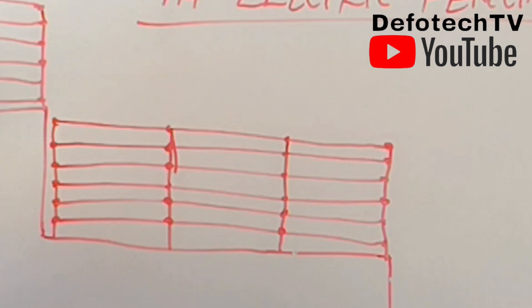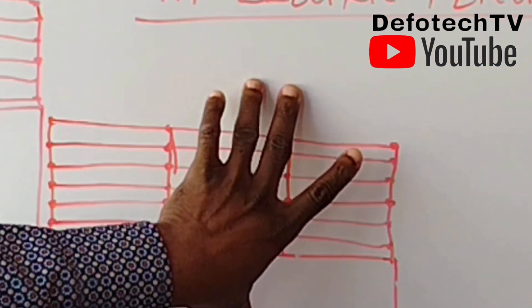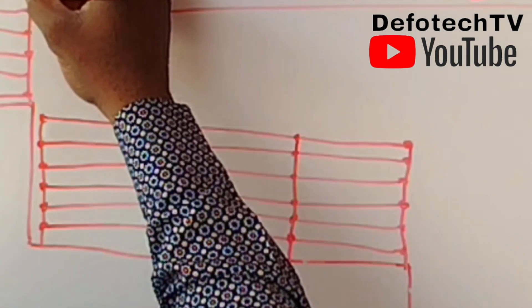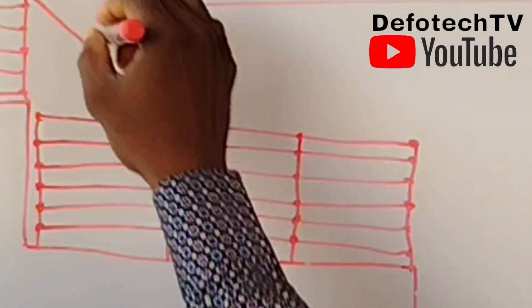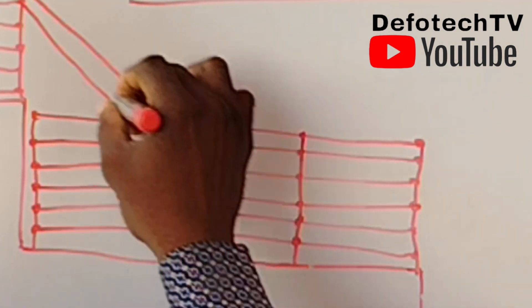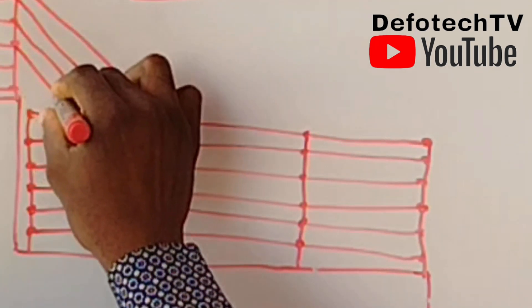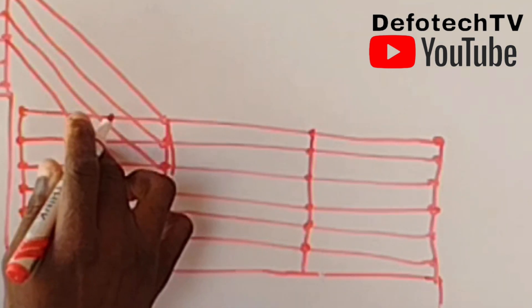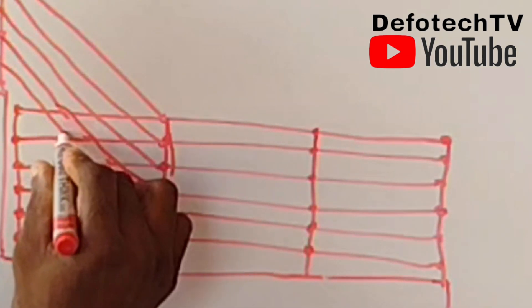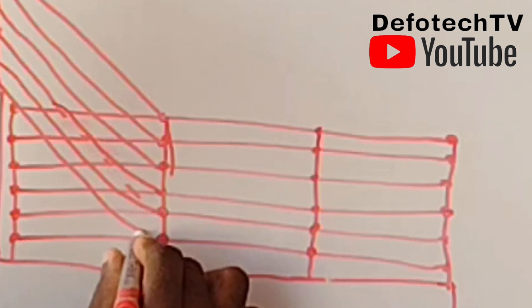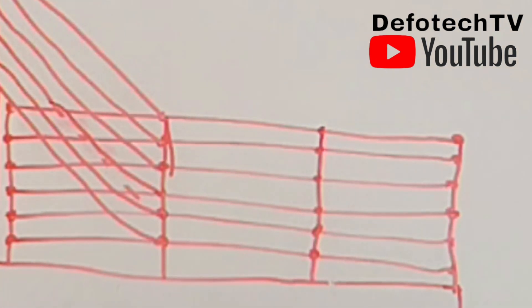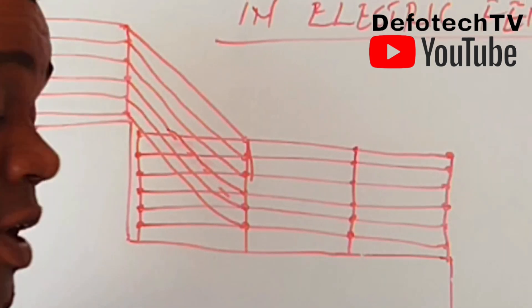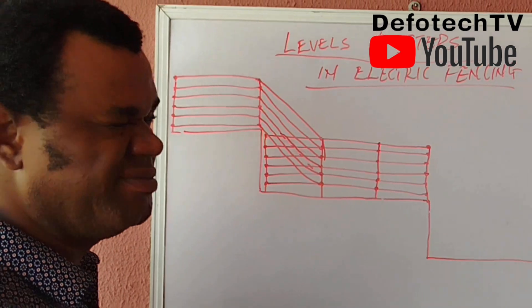Now these people want to link up this top section with this bottom section. One thing I always tell you — this is what we see most times. Some of them just come like this: take line one from here to there, line two, line three, line four, line five, and sometimes take this to line six. Whenever I see this kind of looping, anywhere you see this kind of looping, I'll tell you for free that it is totally wrong. When I see it, it is wrong.